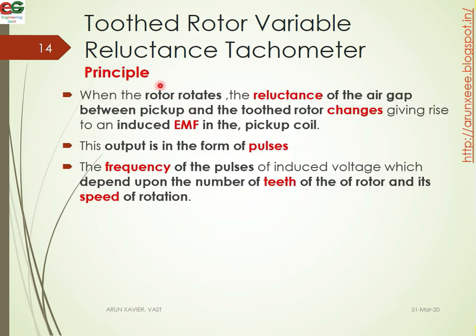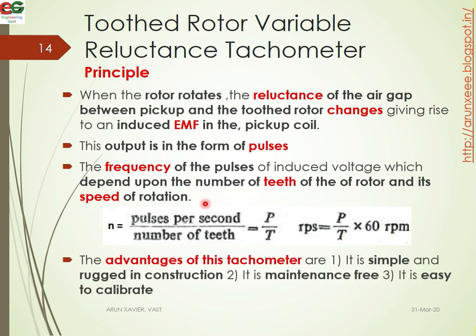After the rotor rotates, the reluctance of the air gap changes because of the toothed teeth. This develops an EMF which is picked up by the coil, and the output forms a pulse. The frequency of the pulse depends upon the number of teeth and the speed of rotation. The equation is N = P / T, where P is the number of pulses per second and T is the number of teeth. Therefore, RPS = P / T, and RPM = (P / T) × 60.